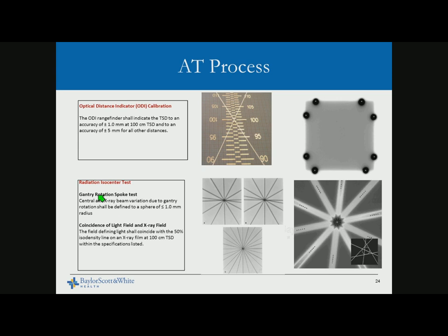Radiation isocenter testing is very important. We do this with star shots — the conventional way using a slit made with collimators. This test varies depending on how well the X or Y jaws are calibrated, but we can still make a good estimate of what the radiation isocenter is.